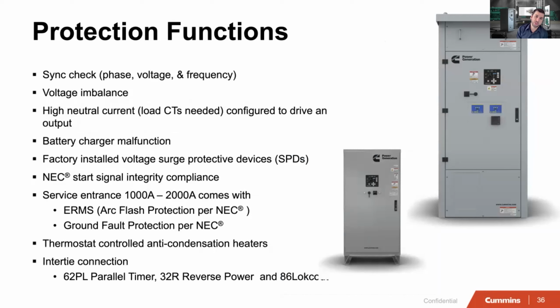Protective functions built into the control. If we're doing a closed transition operation with the utility, there are sync checks: phase, voltage, and frequency, voltage imbalance, high neutral current. There are factory installed SPDs on either source, or it could be on both sources. The start signal integrity is important for life safety applications as well. And for service entrance, the arc flash protection per NEC, the National Electrical Code or NFPA 70, and ground fault protection. There are thermostat controlled anti-condensation heaters, depending on the environment that you're installing the transfer switch in. And for intertie agreements and connections, there are multiple protections in there, for example, a parallel timer that is independent from the control, an 86 lockout, and a reverse power relay.